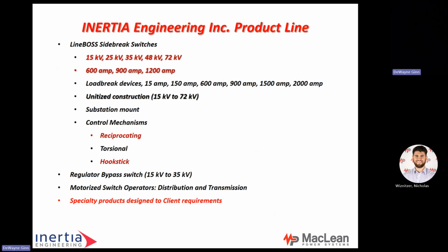Again, there's a regulator bypass switch. It comes at 15 kV up to 35 kV up to 1200 amps, so 600, 900, and 1200 amps. Motorized switch operators for distribution and transmission, and I'll show you those in a later slide. And again, we can do specialized products designed for the client. If they have a special one-off they need, or it needs special phase spacing or some other thing that they need on a switch, we can do that.